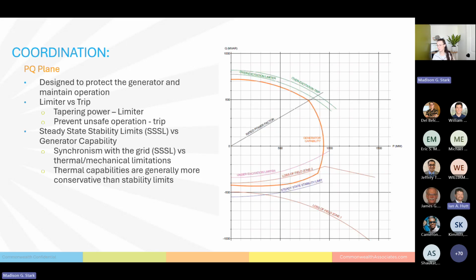The first example of coordination, the most common example and one of the easier ones to understand, is the PQ plane, or the power graph. This is really the power capabilities of the generator. On your vertical axis, you have reactive power, and on your horizontal axis, you have real power, so VARs and watts. This orange curve is the generator steady state capability. So this is what it can safely do for a sustained period of time. And in this plane, we see how we protect the generator and maintain operation as far as power output capabilities.